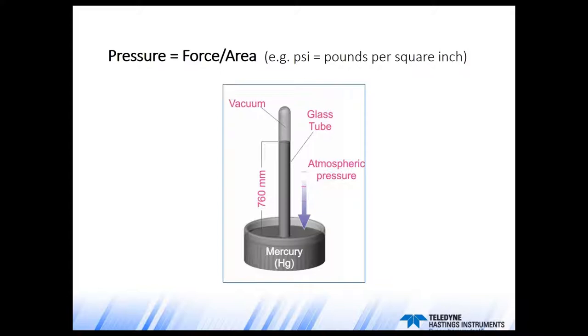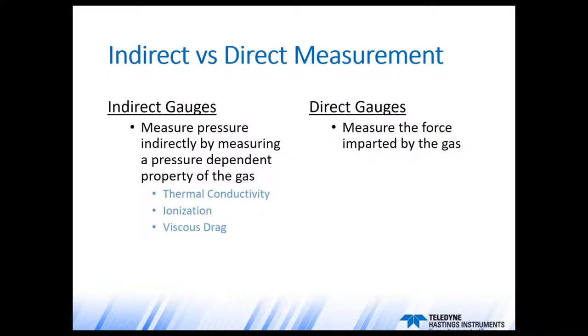Now I'd like to get into another topic: the characterization of gauges as being either direct or indirect. Pressure is defined as force per unit area — think pounds per square inch, or the old mercury column where atmospheric pressure pushes mercury up and you measure the height, 760 millimeters of mercury. Direct gauges measure the force that the gas imparts on some part of the gauge. Indirect gauges measure pressure by measuring some pressure-dependent property of the gas, such as thermal conductivity, ionization rate, or viscous drag.